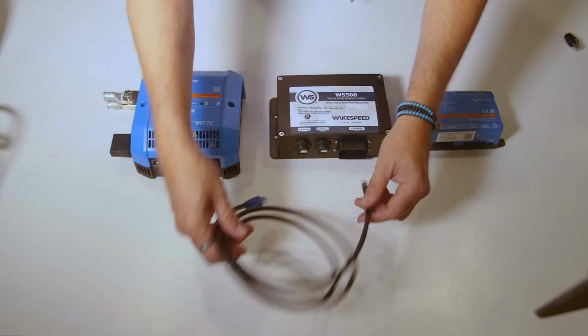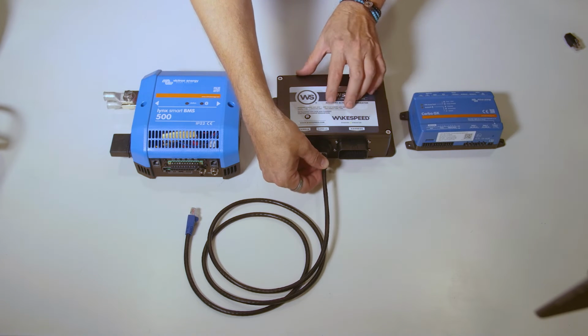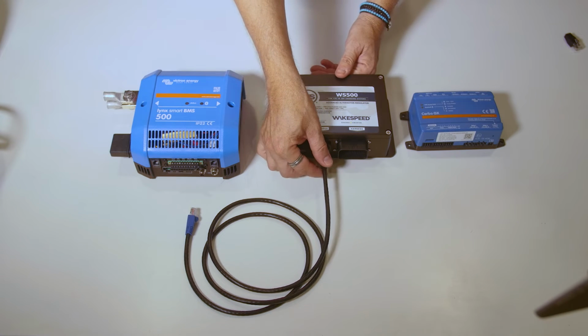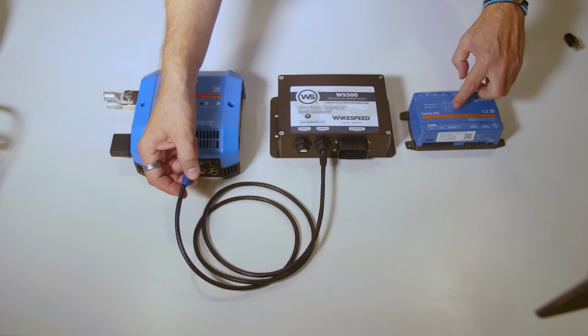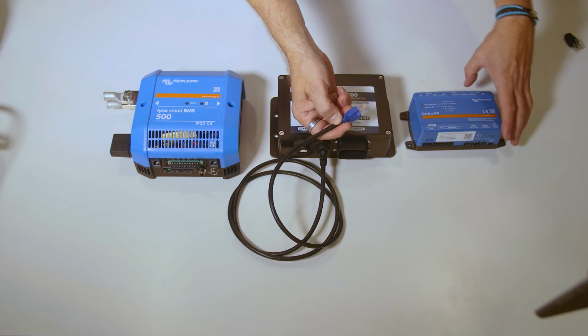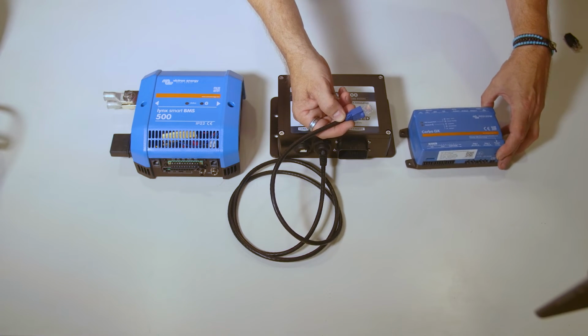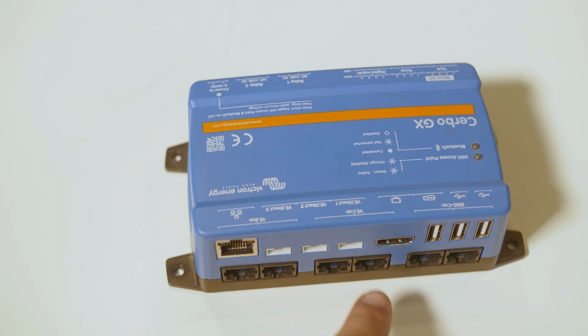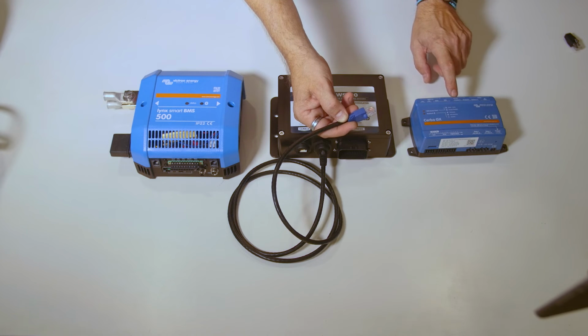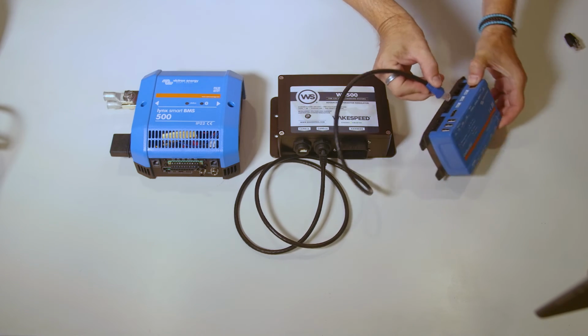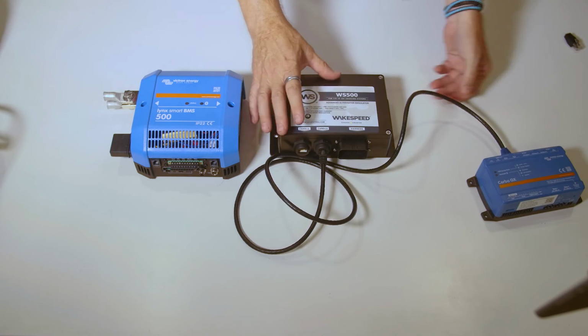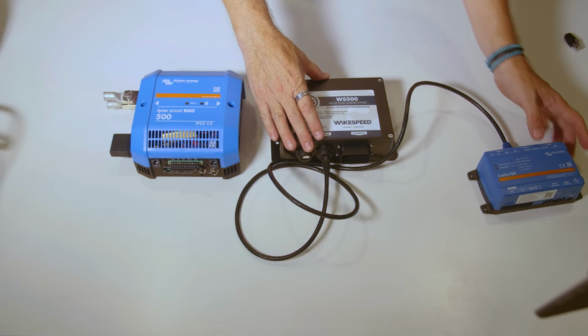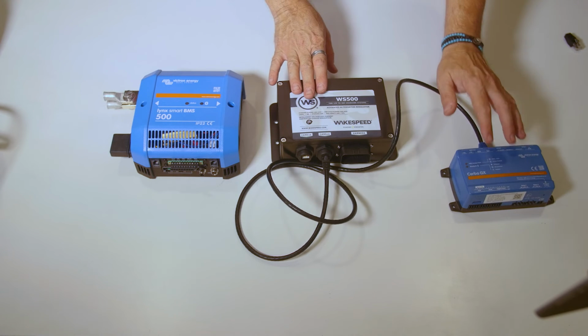You're going to take one of the RJ45 ports, doesn't matter which one, on your Wakespeed and plug in the black side, and then on the Cerbo GX, plug it into a VE CAN port. It's very important to distinguish between VE CAN, VE bus, and Ethernet because they all use the same RJ45 style connection. So VE CAN is here, going to plug that in. Now we've created a communication between the Wakespeed and the Cerbo.